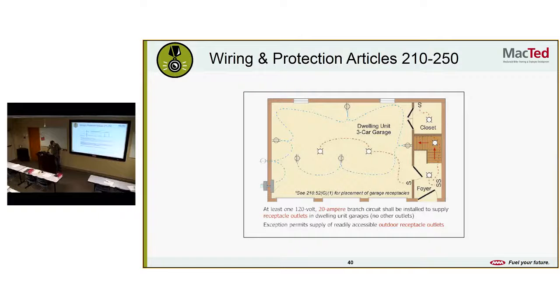Looks like there's a picture here. Typical garage. So you should have at least one 20 amp, 120 volt outlet, dedicated circuit for your garage. Showing it on the picture there, it looks like there is an exception to supply an outdoor receptacle off of that garage circuit. Any questions on that? Pretty straightforward. More power. You want more power out there anyways.